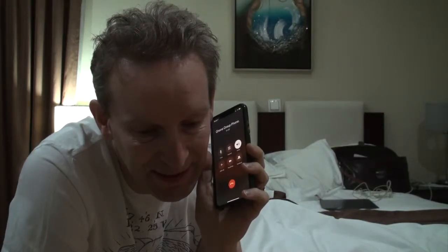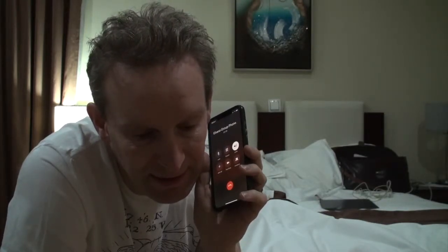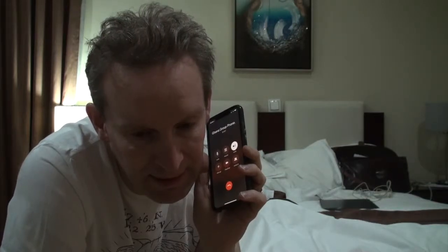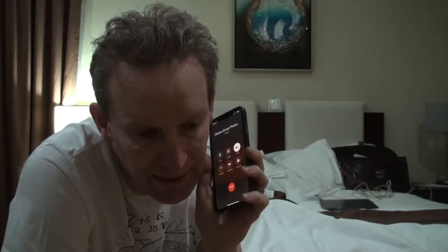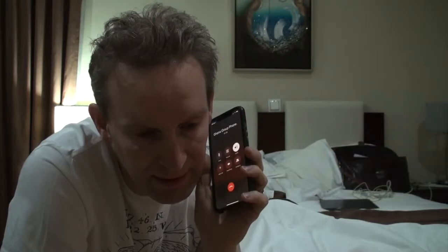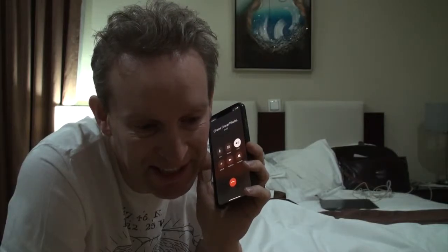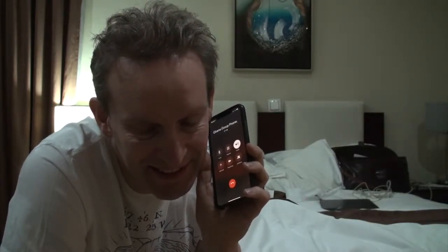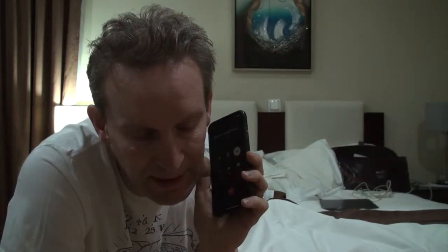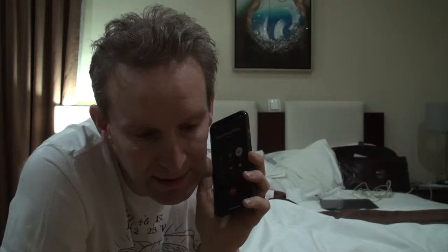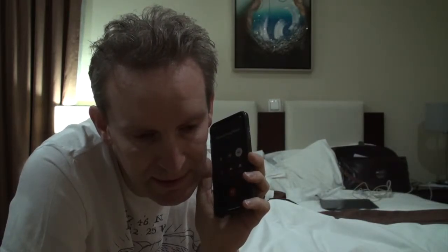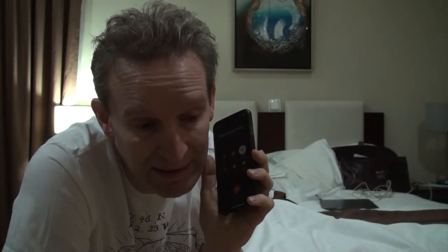But the only thing is we need to be aware of the fact that we only have one connector from the oxygen cylinder to the ventilator, so we can't have 2 patients on ventilators at the same time. That's all. Okay, that's pretty important if we're going to try and do 2 cases today then. Exactly, yeah. So this is a problem apparently, because he was saying we might not get any sort of notification of that. So suddenly the oxygen supply goes off, and then we have to get these big cylinders. So that's one thing that he was mentioning, and apparently one of the patients died in the mission because they couldn't get the oxygen in time.